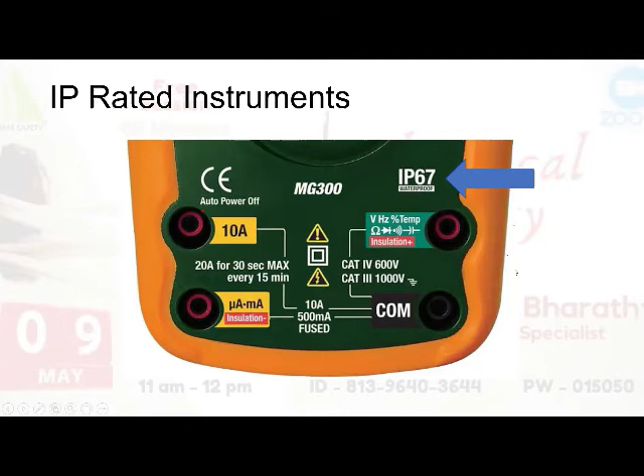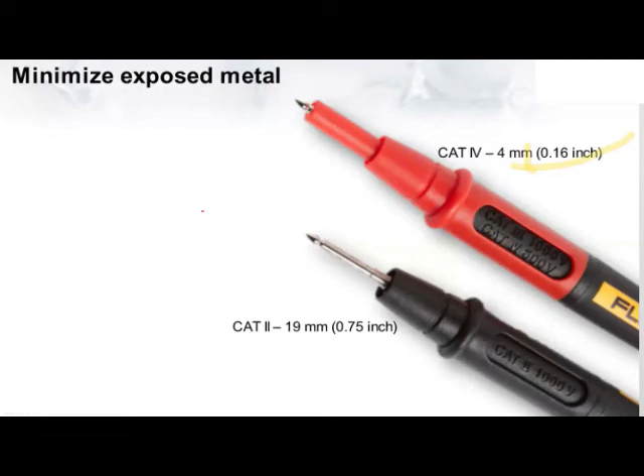We talked about the probe - it is very important. For category 1 and 2, there is a different kind of probe where the metal exposure will be more, like around 1 inch or half an inch. For category 4, the metal exposure should be a maximum of 4 mm. So we have to choose the probe accordingly - not every electrical wire can be used with a multimeter. Please avoid that. Let me make a video to give a clear picture.